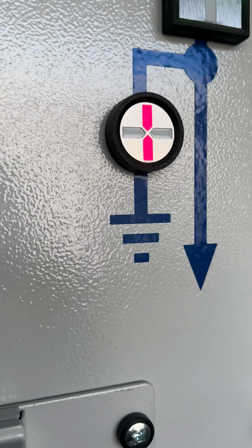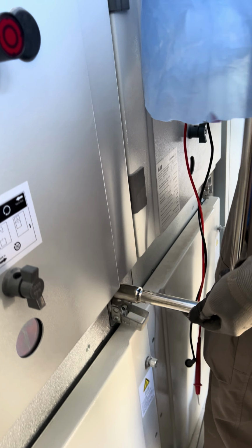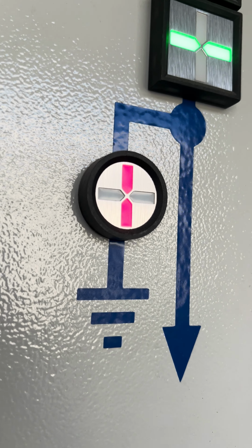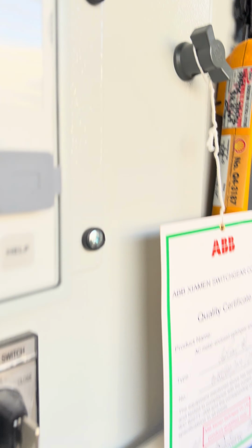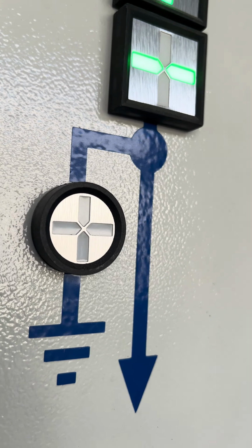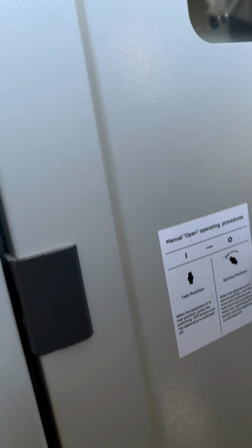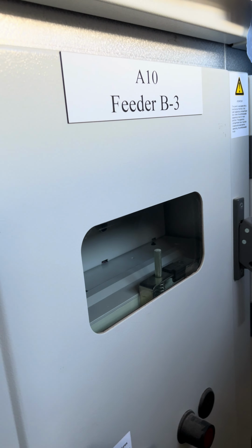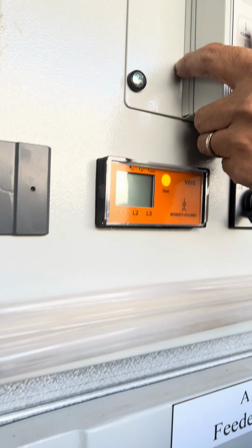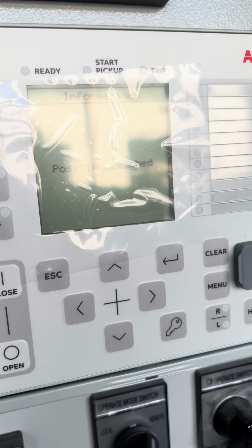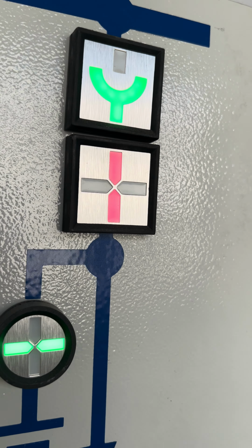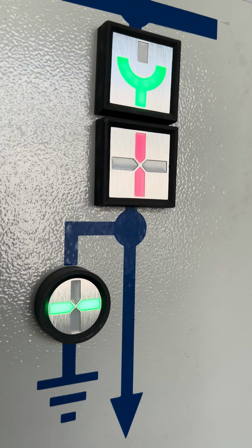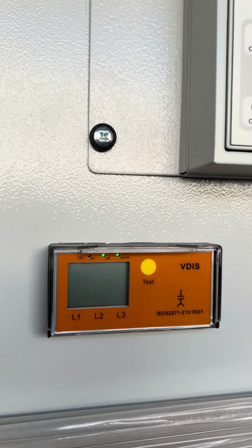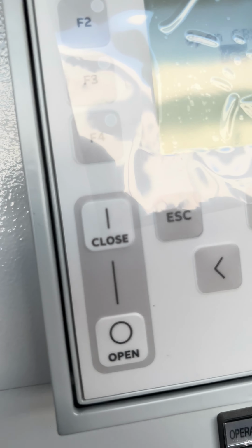Okay. So so that we can operate the vacuum circuit breaker, we have to manually open the earthing switch. So we have to manually open that one by locking in, locking out. Okay, now it's open. Okay, it's open. The earthing switch is open. And we can now operate the vacuum circuit breaker remotely. So because we have switched the remote. Okay, see? So the motorized control is operating with circuit breaker in closed position. So now we are commanding at open.